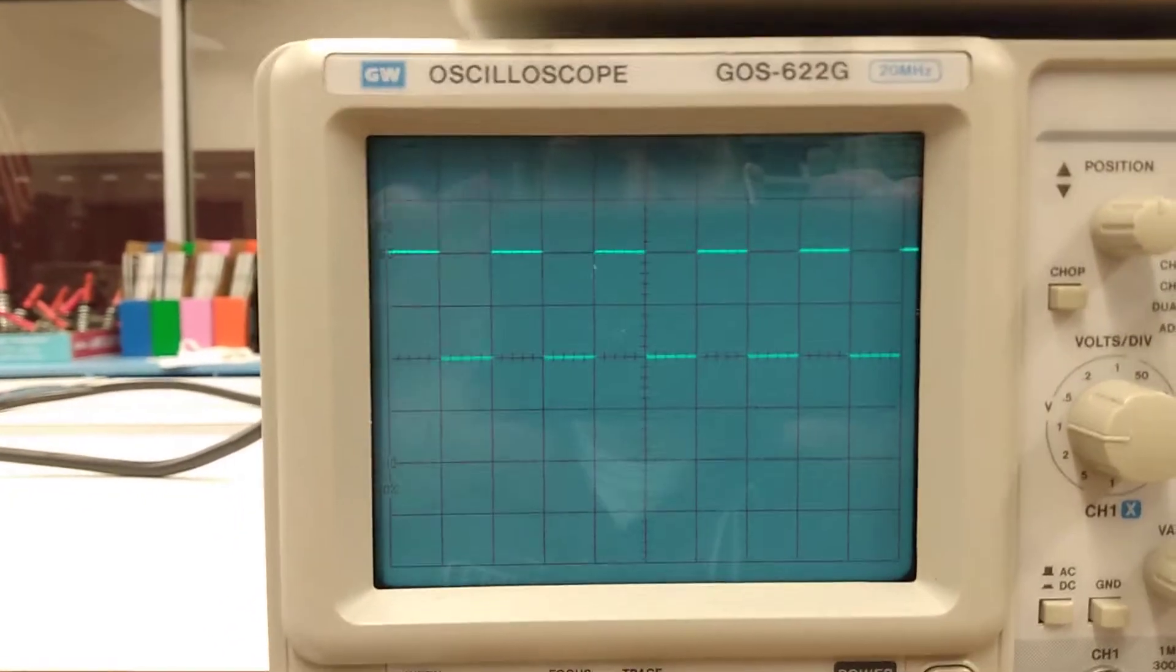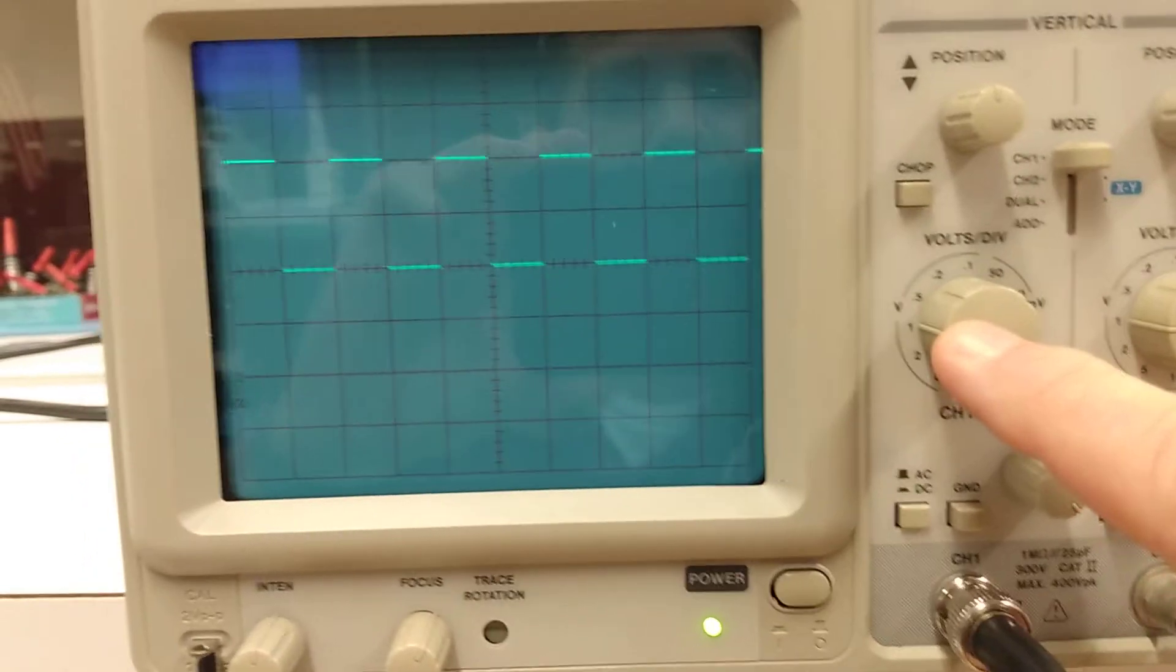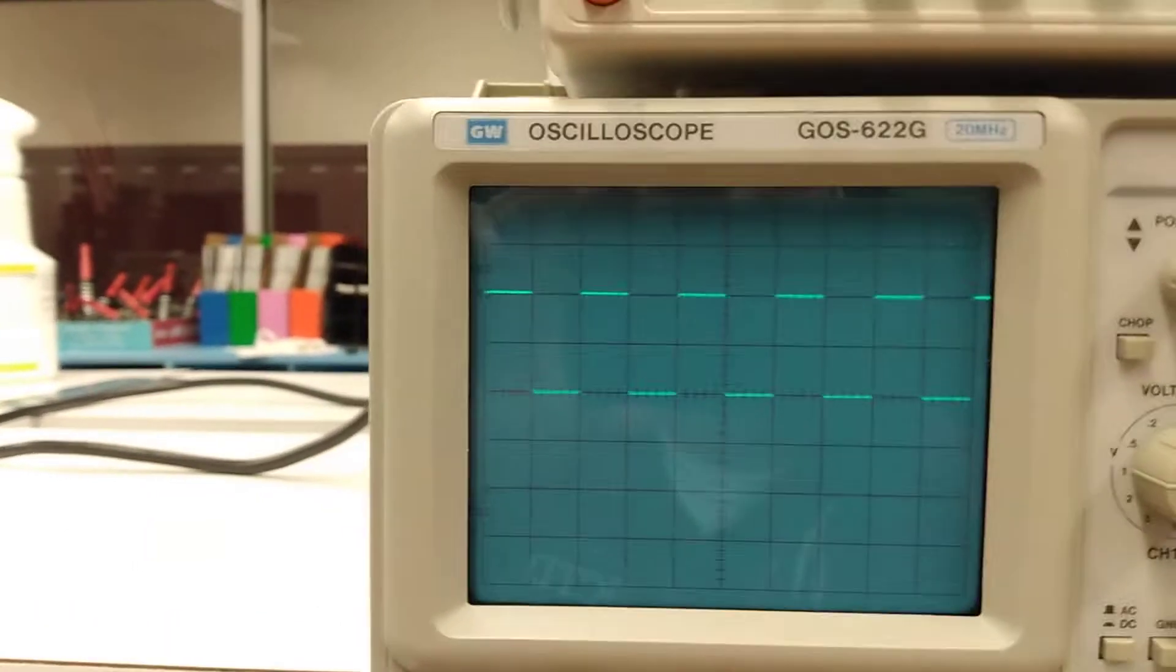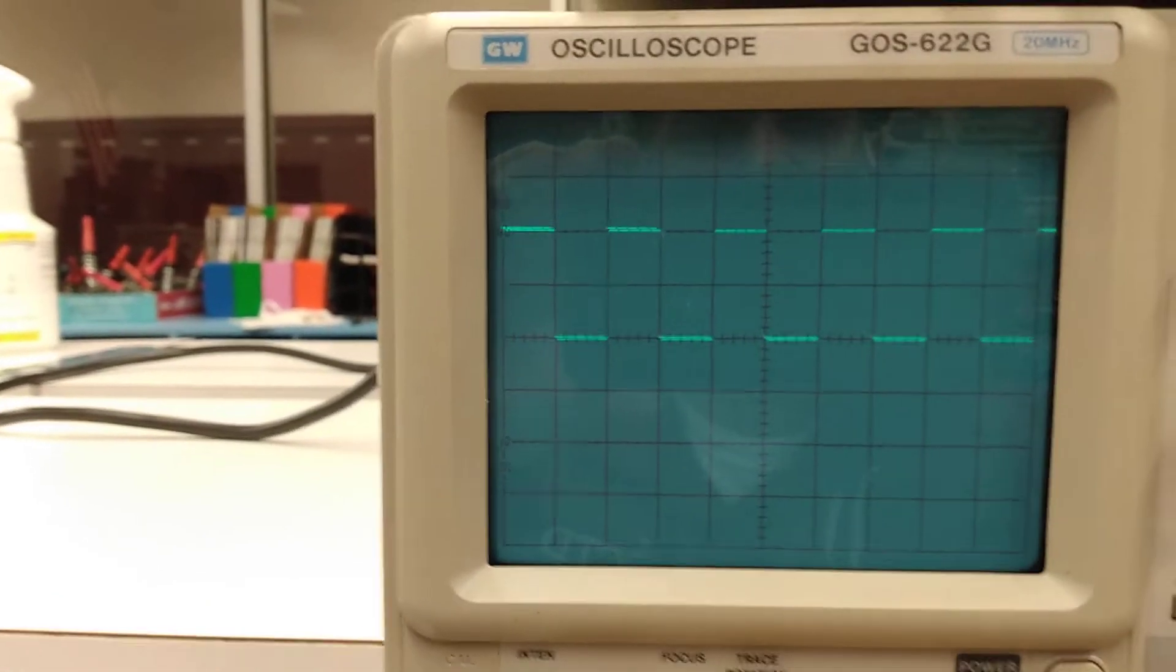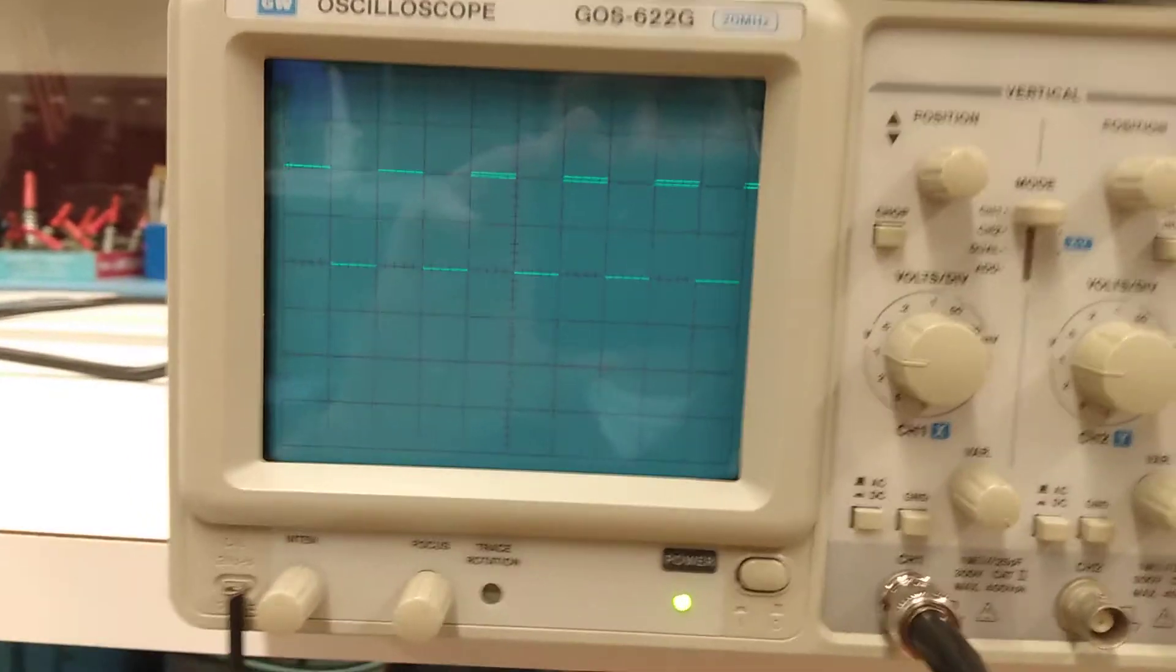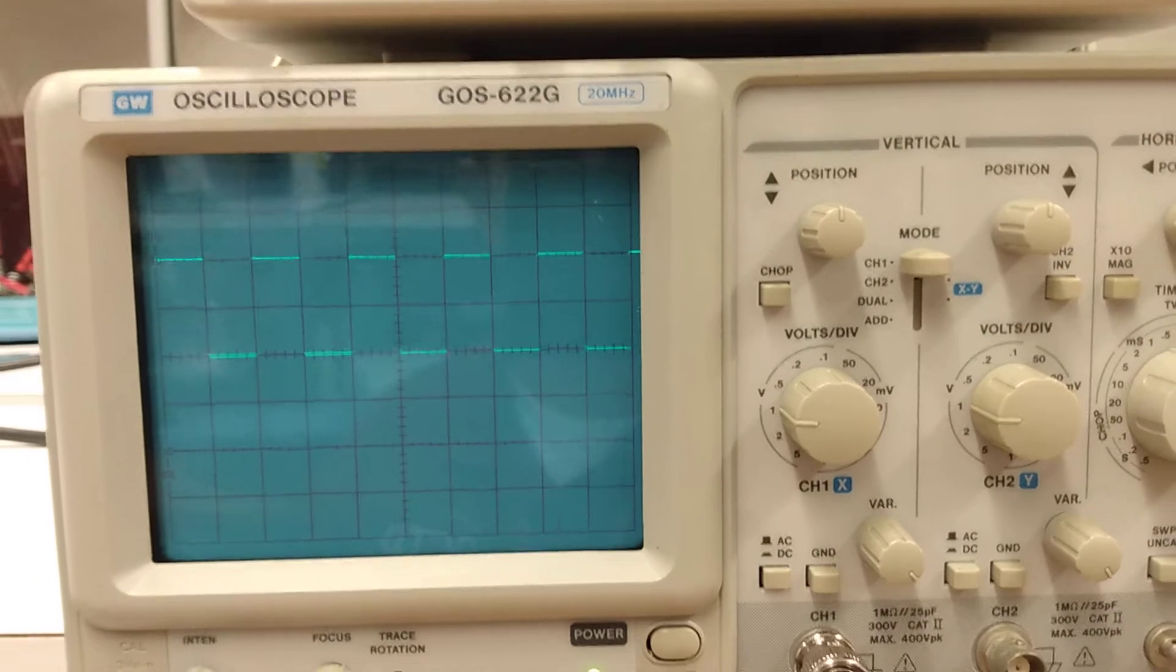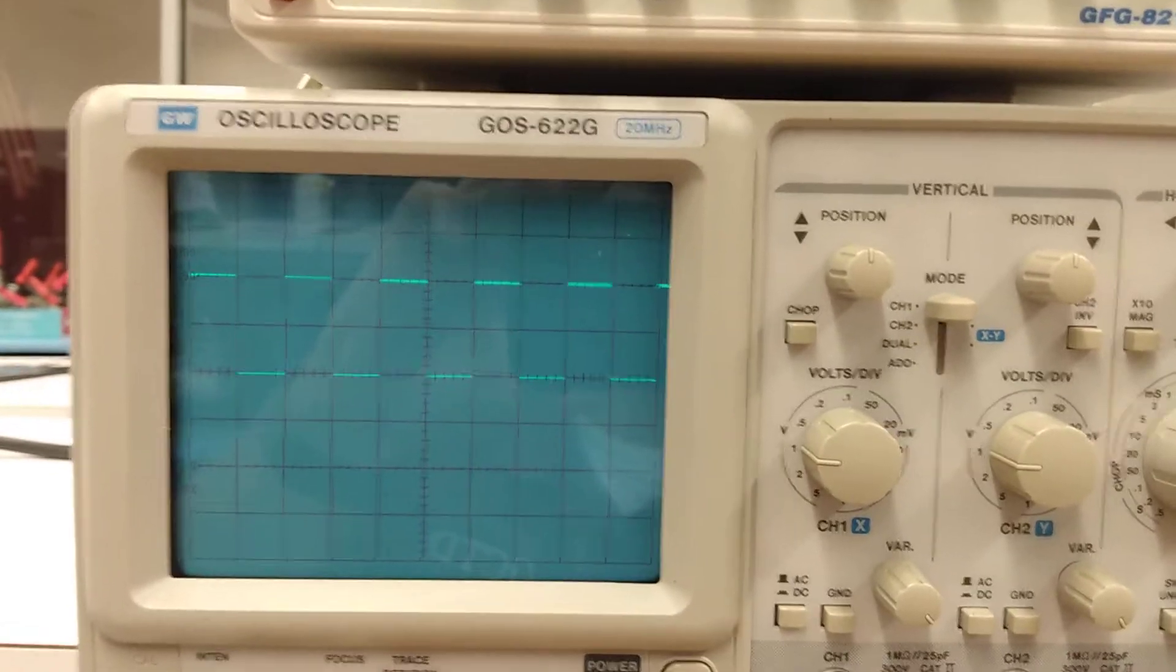Now remember our calibration should be 2 volts peak-to-peak. When I look at the division setting over here, I'm at 1 volt per division. So that means 1 square equals 1 volt in the vertical direction. So 1 square, 2 squares - that's a 2 volt peak-to-peak top and bottom signal. So we're at 2 volts and I'm at a 1 kilohertz frequency.